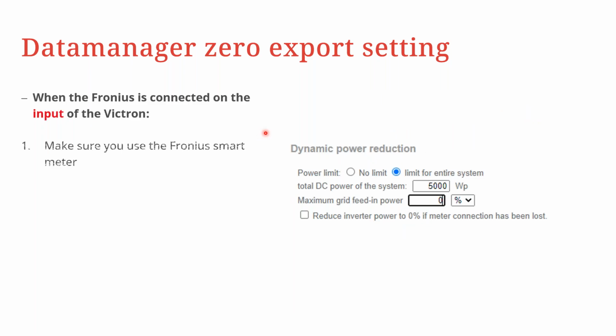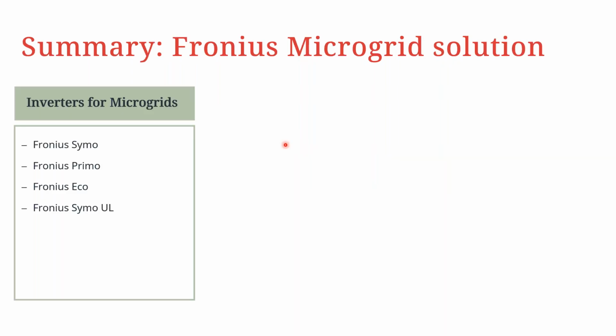For inverters that are connected to the AC in, you have to use the Fronius Smart Meter and ensure that you activate the dynamic power reduction within the web user interface of the data manager. And you enter 0 as your preferred percentage of how much power should be going to the grid.